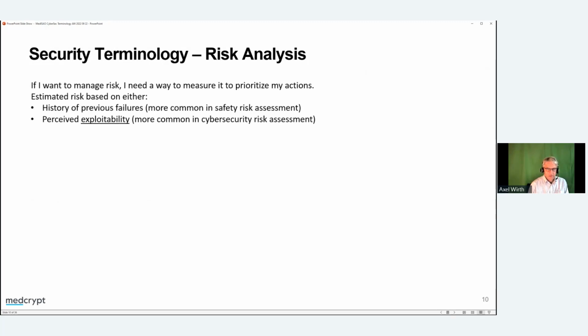Now, if we talk about analyzing cyber risk, we need to understand that in cyberspace, we're not dealing with statistical events, right? Unlike in traditional safety risk management, where we have data, for example, from field devices or data obtained through destructive testing of devices, we don't have that background in cybersecurity. Therefore, we may talk about probability, certainly, but the interpretation of probability is typically different as we're looking at how exploitable a particular component or a particular vulnerability is. Whether it has happened in the past, whether there's any historic evidence of that vulnerability being compromised, doesn't matter. If there's a vulnerability, its risk exposure to compromise in the future is based on how easy it would be to compromise it. Whether it has happened in the past or not doesn't matter.